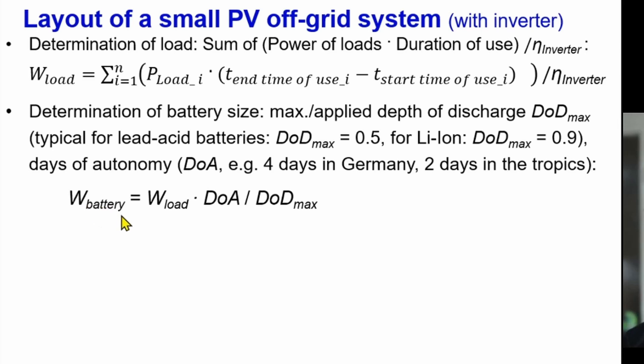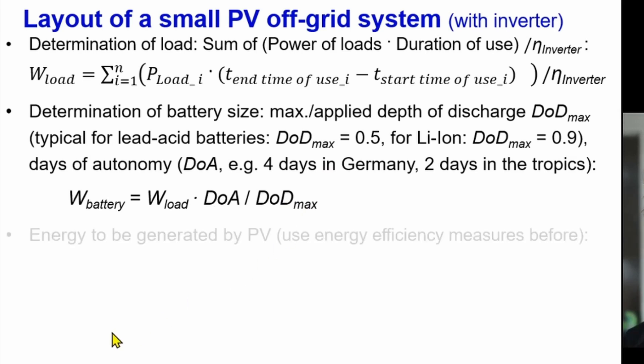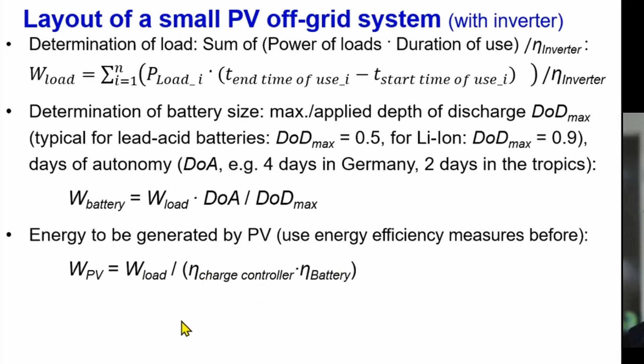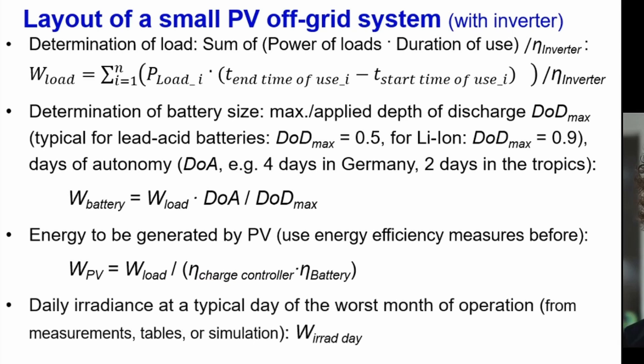The energy to be stored in the battery equals the energy needed by the load multiplied by the days of autonomy, divided by the maximum depth of discharge. The energy to be generated by photovoltaics must also account for battery efficiency and the charge controller efficiency. We take the daily irradiance for the worst month of operation — typically the worst month of the year, or the relevant season for specific applications like irrigation.